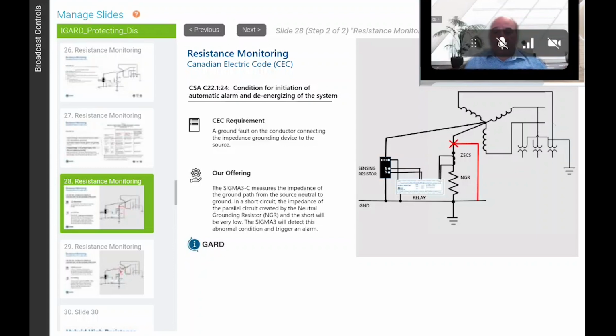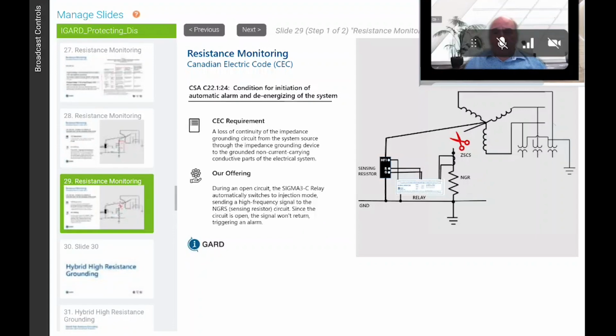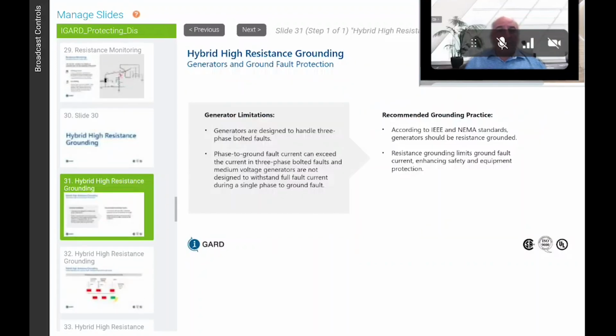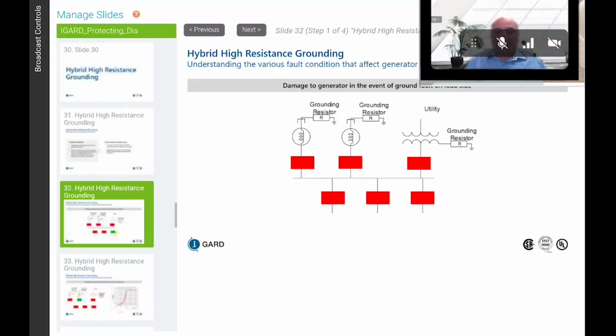So basically we're looking at a short circuit in the neutral or an open circuit in the neutral, right? So we monitor that integrity. And if you notice, we have to have a second connection all the way back to the source neutral, because I have to verify this continuity from the transformer neutral to the resistor. So the high resistance grounding system is specifically designed for medium voltage bus connected generators. And here's an example of a medium voltage bus connected generator. So we have 400 amp, 10 seconds, medium voltage. So you're looking at 13.8 kV generators or whatever.